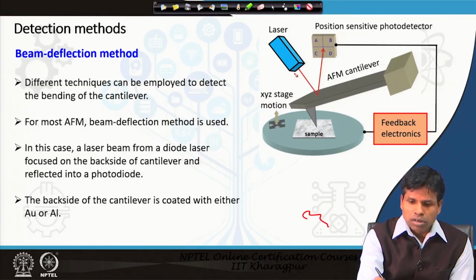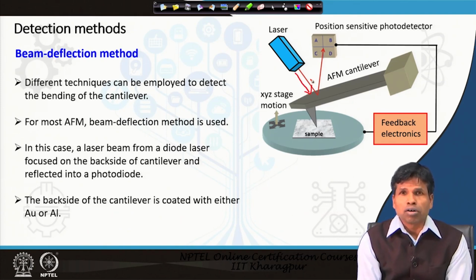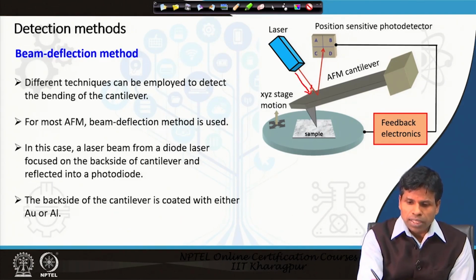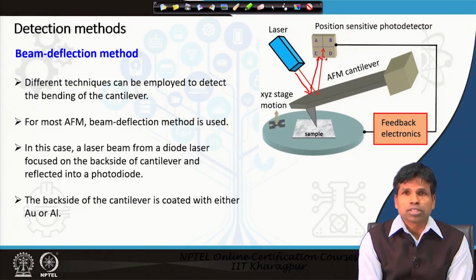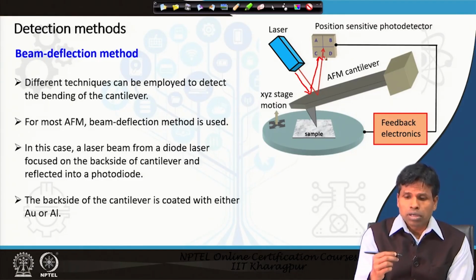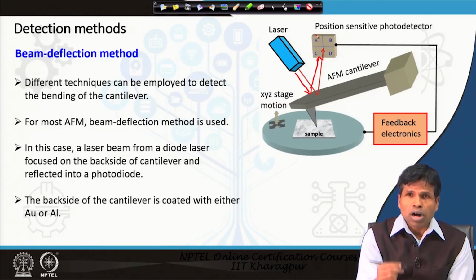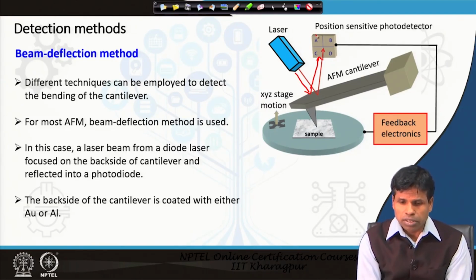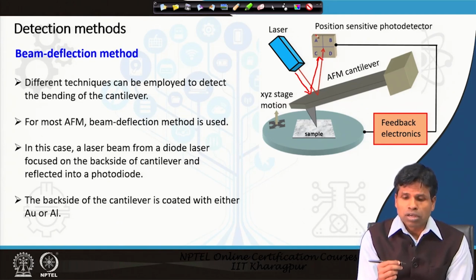In the beam deflection mode, as you see here, a laser beam is striking the back side of the AFM cantilever, and then it is deflecting back to a position sensitive detector. As the cantilever goes up and down, the beam position will go up and down in the position sensitive detector. With that we can measure how much the cantilever is bending upwards or downward, and thereby know the height or topography of the sample across the surface.